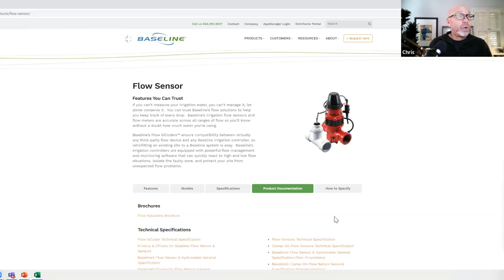Probably small, if they're asking about minimum flow. On the tech spec, we rate maximum rated flow for all sizes, but for minimum flow, we only rate it for 3-inch to 8-inch. So if you've got one smaller than 3-inch, we'd have to dig into that, or we can link you to a website with that additional information. For general purposes, the IDFS will read a lower flow than an impeller style flow sensor, so it reads very, very low, probably lower than is required unless you're looking for something like a droplet.